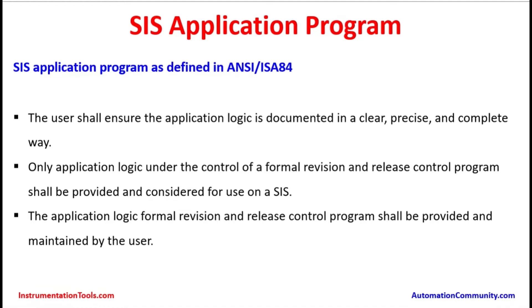There may be multiple versions coming on the programs. Every time there is a revision, that has to be properly maintained and updated. There could be small changes or major changes, which have to be recorded and updated, and the earlier version of the program before any change has to be saved in a separate portable media. That way, if there is any chance of a program getting corrupted or any error occurring during downloading, the user can recover from the old program.